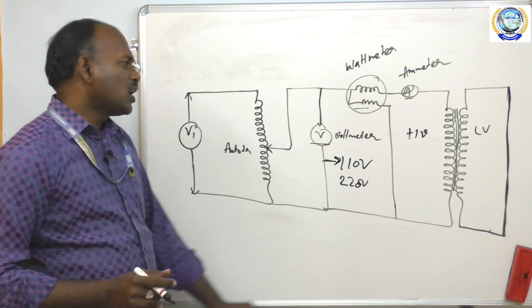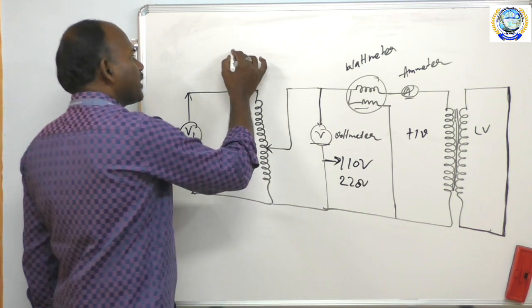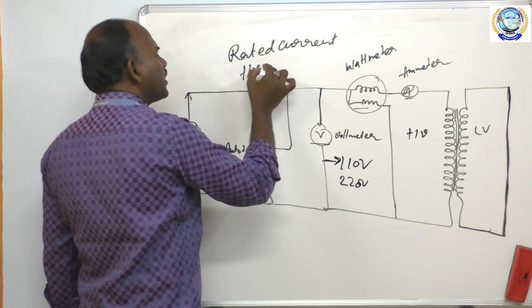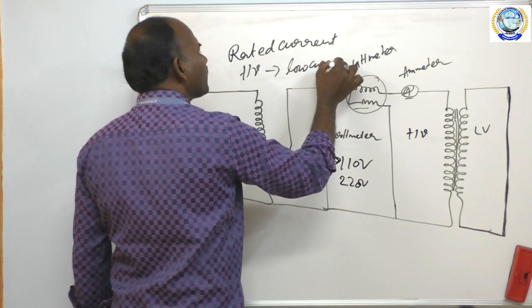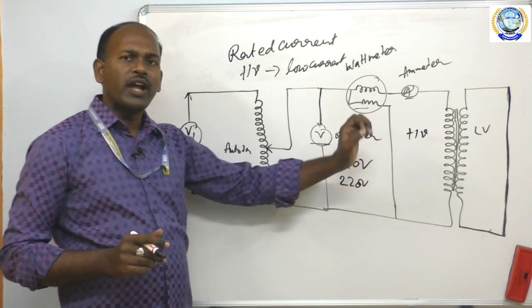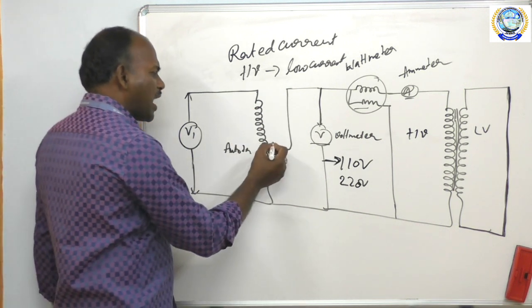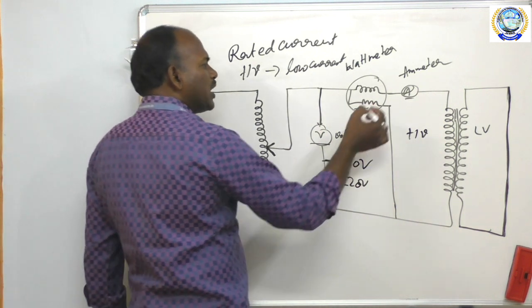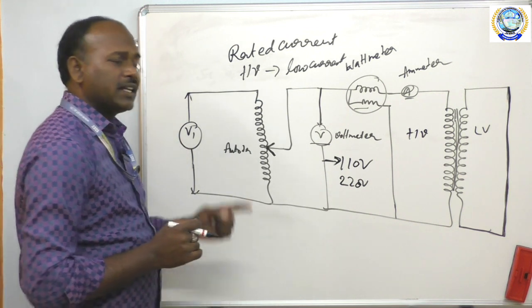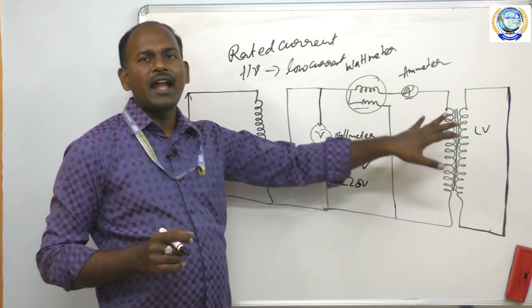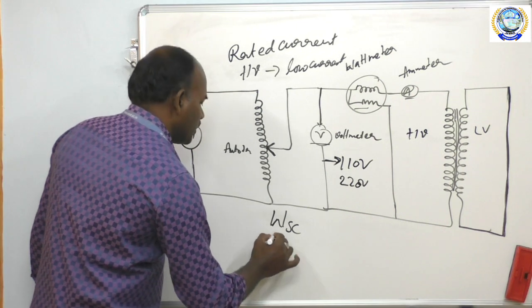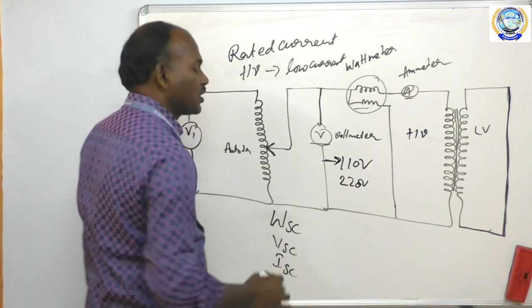Why connect meters on the HV side? Because here we have to apply the rated current. When the high voltage side has low current, we connect meters on the high voltage side to get a lower value of current. You vary the auto transformer until the ammeter reading gives the rated current value, then take a set of readings of voltmeter, wattmeter, and ammeter — giving Wsc, Vsc, and Isc.